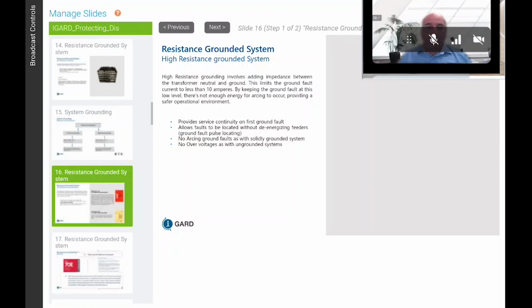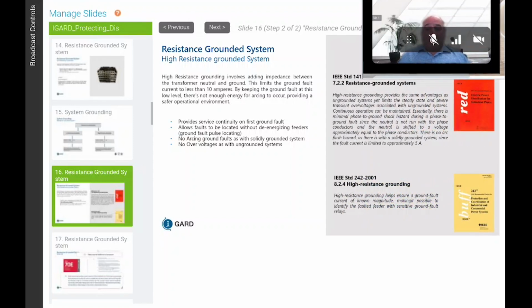And again, on a low voltage system, I've never seen a capacitive charging current greater than 1 amp. And 1 amp was rare. So high resistance grounding provides the same advantage as ungrounded systems. You don't have to trip. The voltage vectors behave the same way as in an ungrounded system. However, the maximum voltage you can have phase to ground is 173% of your phase to neutral voltage, as with ungrounded systems.